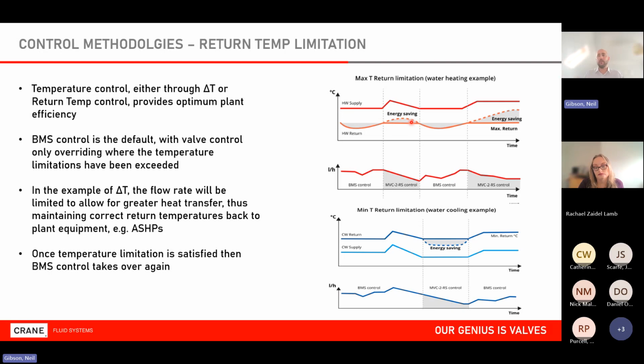And to use an example, if it's a heat pump system, a 55-degree flow and a 45-degree return, if it creeps up and it starts to look like 46, 47, reduce the flow rate, maintain that 45 degrees until it falls back below, so you get a good delta T. Once that is satisfied, BMS control goes back. And this is all automatic. All I have to do is input that return value. So I'm protecting things like the heat pumps, which are quite precious, over the temperature that they get back and their delta T's and return temperatures. I protect the system from delta T syndrome as well. And I can monitor all of this information on a continuous basis to see if there's any trends that I need to investigate as well.